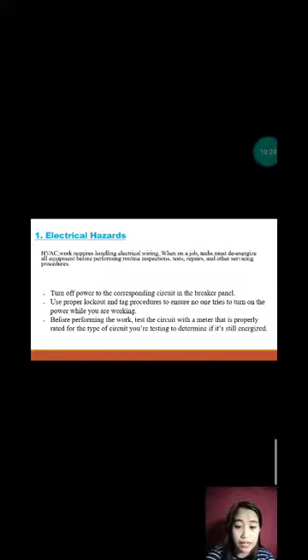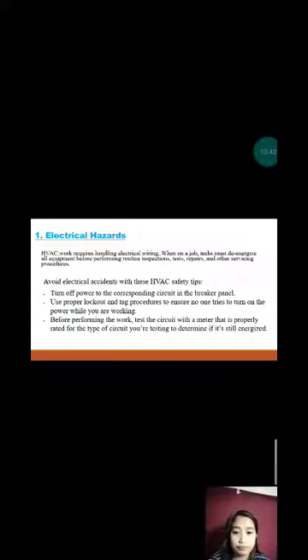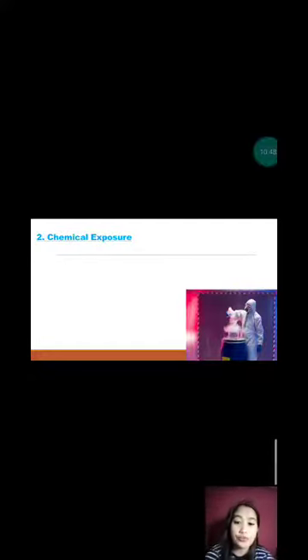Use proper lockout and tagout procedures to ensure no one tries to turn on the power while you are working. Before performing the work, test the circuit with a meter that is properly rated for the type of circuit you're testing to determine if it's still energized. Okay. And next we have to avoid chemical exposure. How to do that?